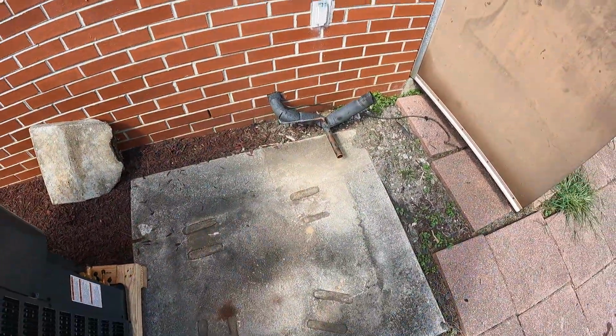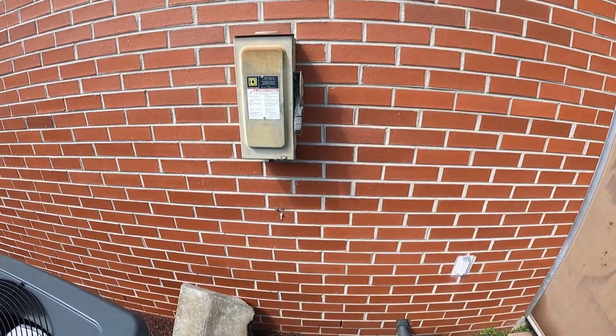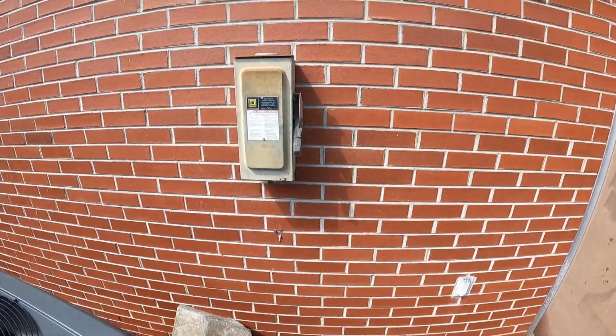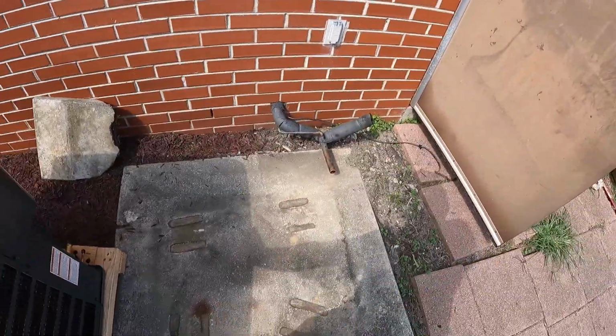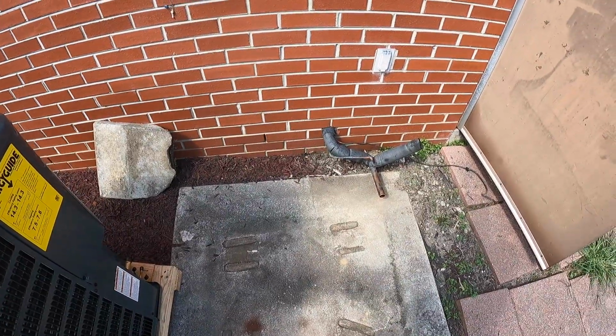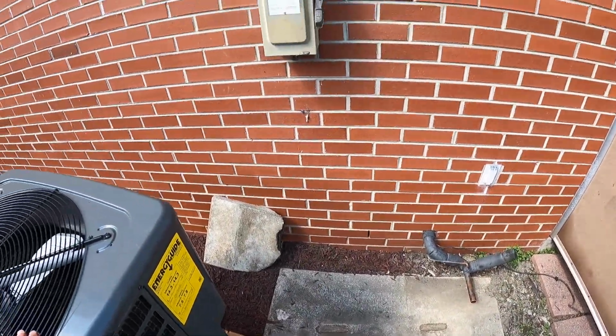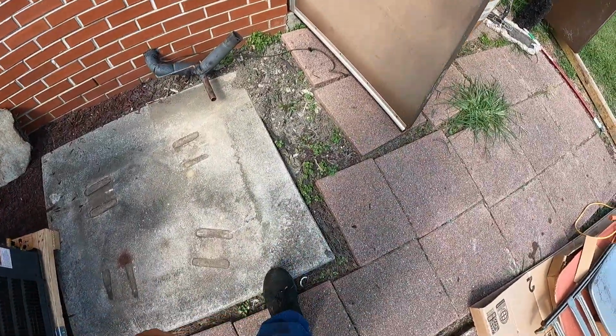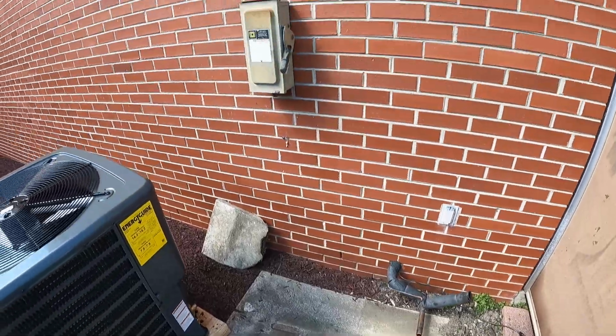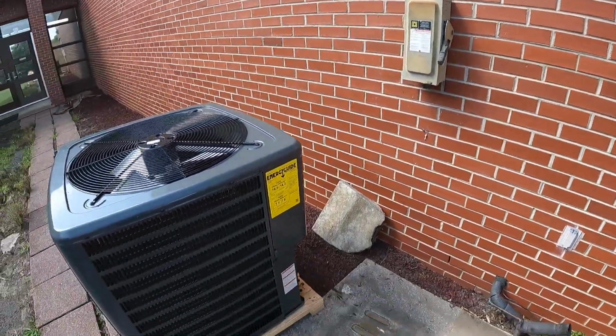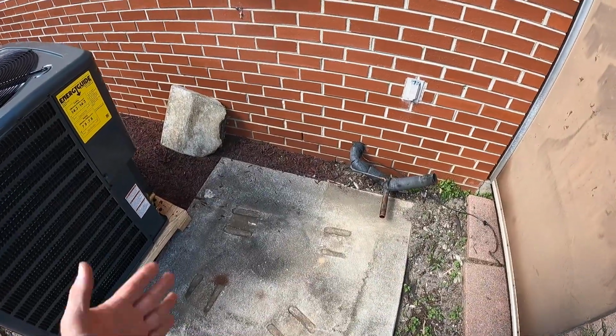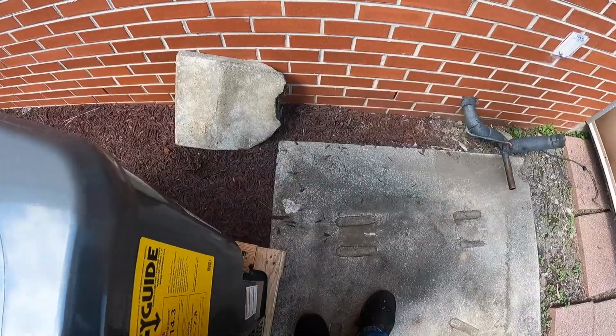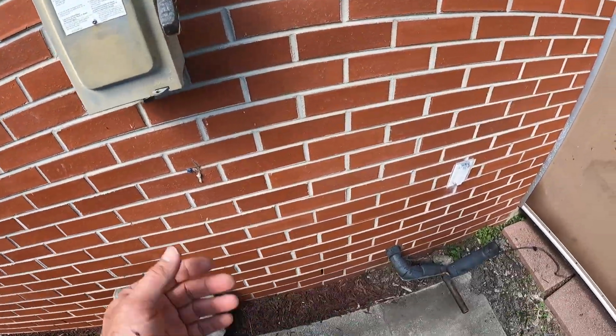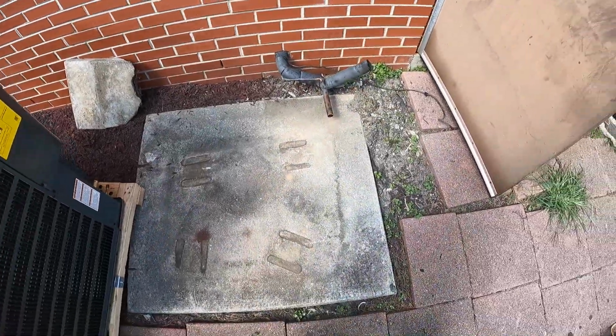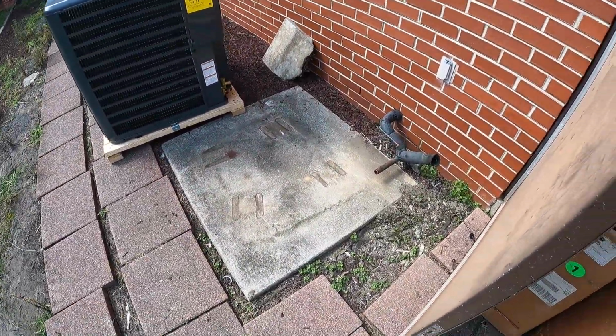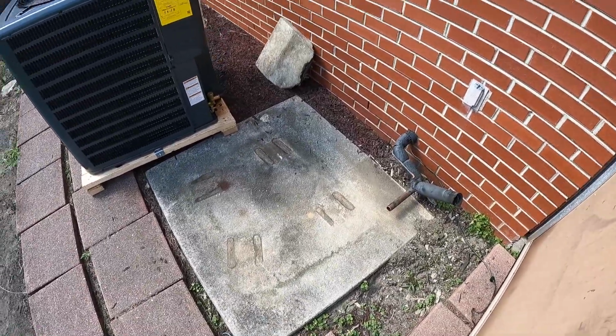But that's going to go here on this pad. Again, we're going to do a new line set. Of course, this pad is poured concrete. That disconnect is mounted on that brick wall, and this was all done with the help of engineers and architects. So I'm going to hold that unit as far this way as I can on this pad to try and leave room in front of that disconnect, because this unit's taller than the old one, and no matter what, the old one was still in front of the disconnect. There's the feet, there's the disconnect. So I mean, you can't rebuild everything. They should have thought about that the first time around. That's a nice level concrete pad though, so I'm going to use it.